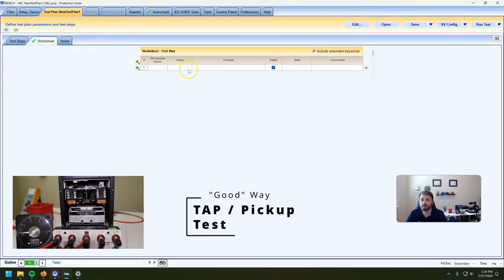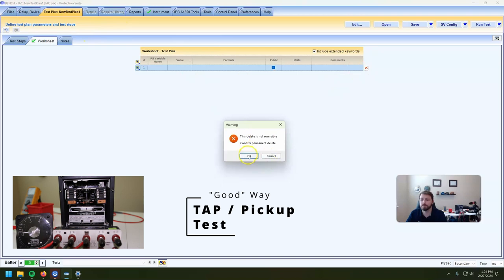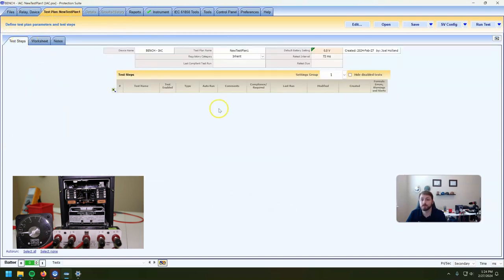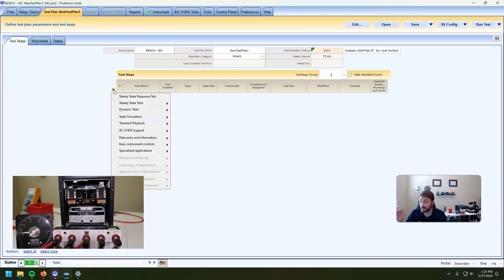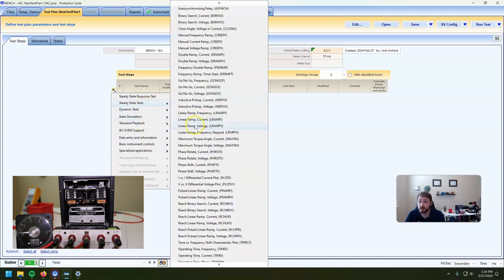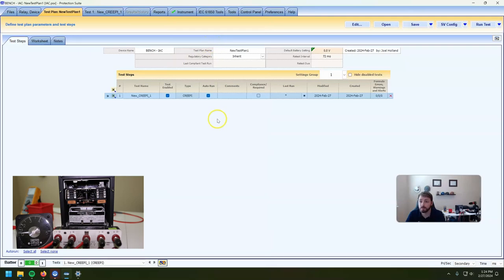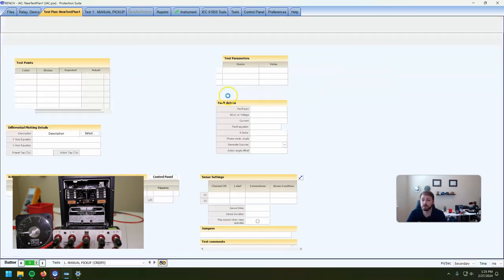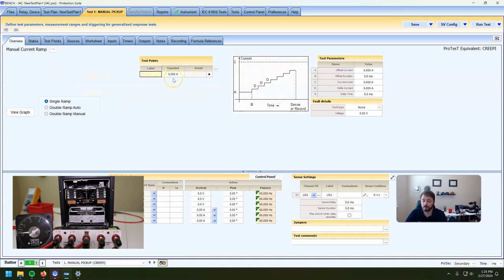So the first test — there's a bunch of different ways to do this. One thing that we can do, I've got it hooked up over here with a little ammeter so we can follow along. We're going to go steady state tests. Let's just do the very basic minimalist manual pickup test. Our expected test point is tap — that's our level. It's four amps, because that's what we set the dial to.